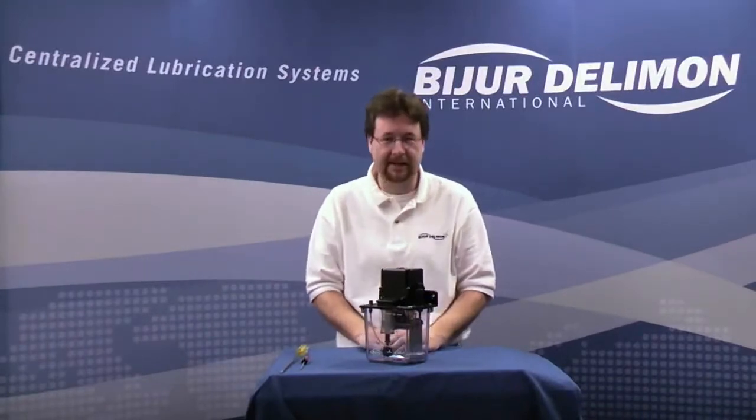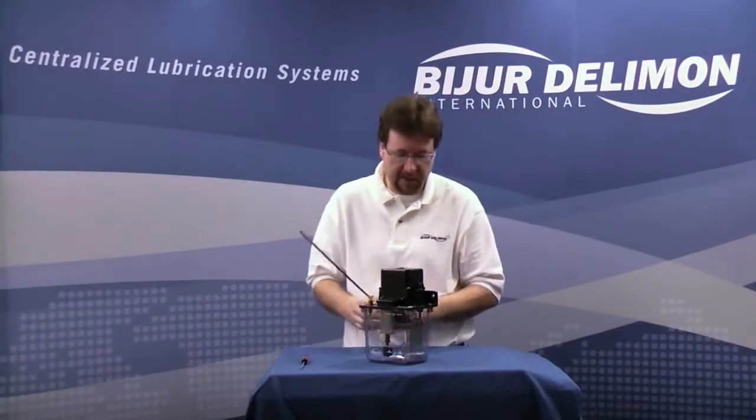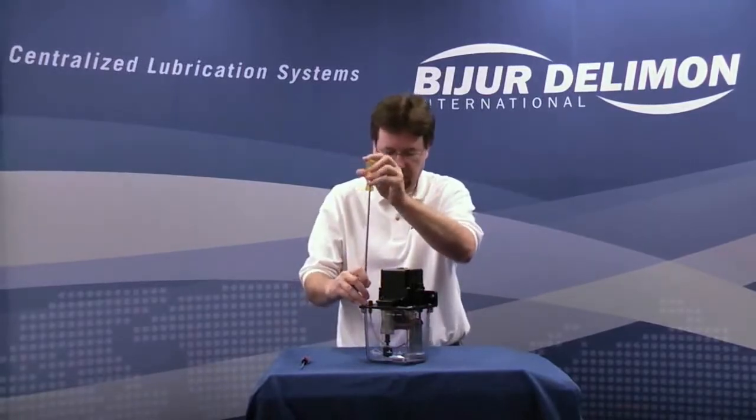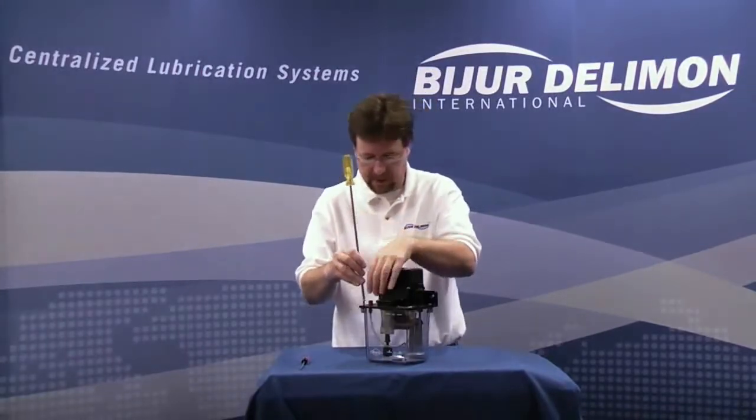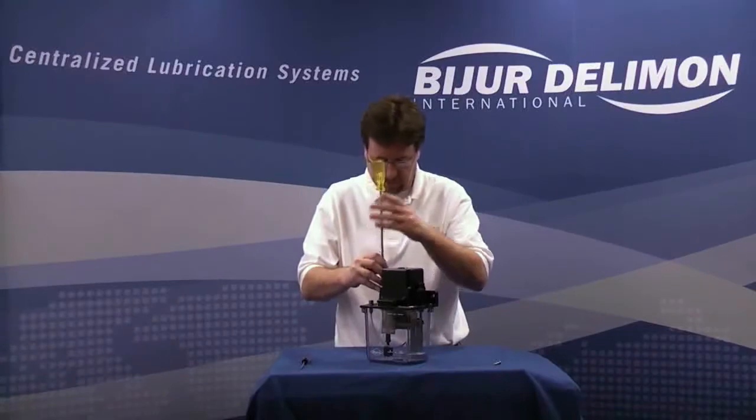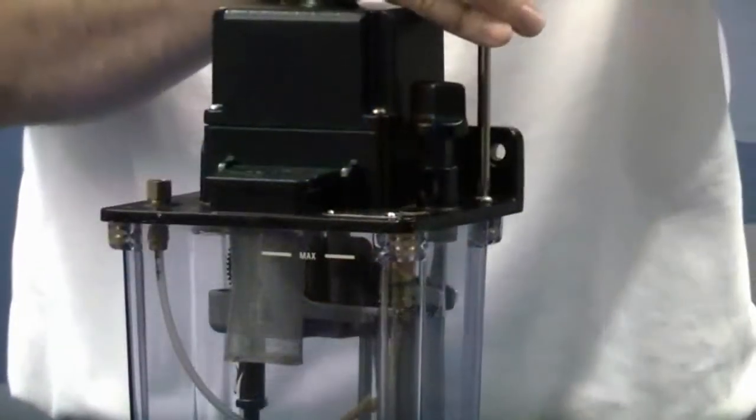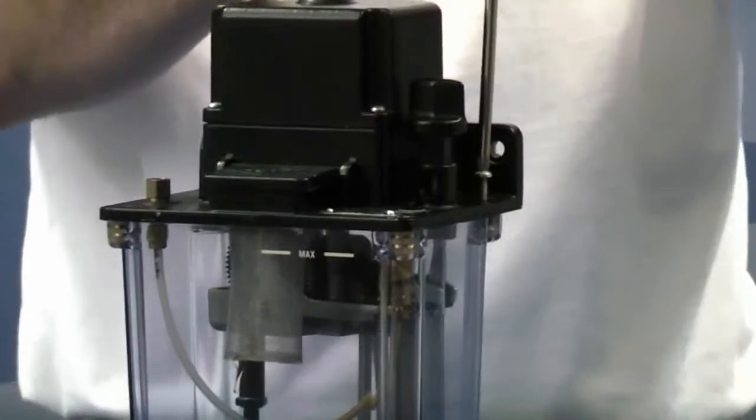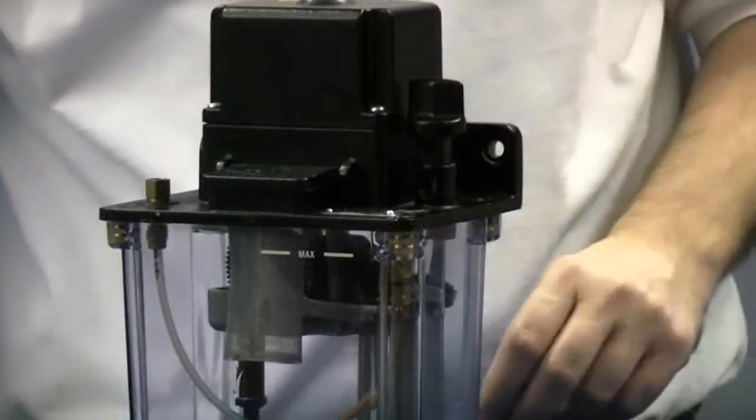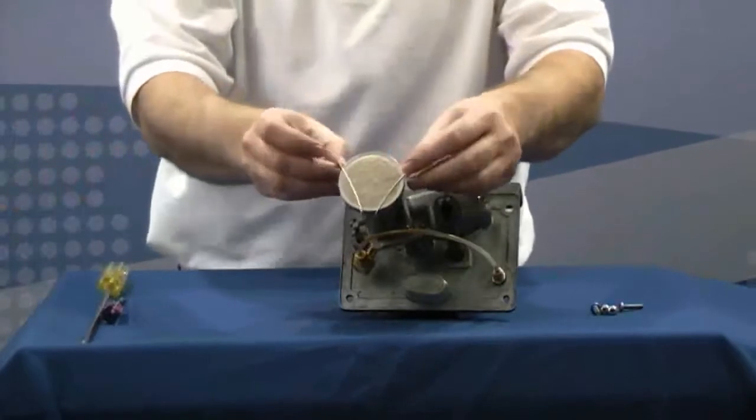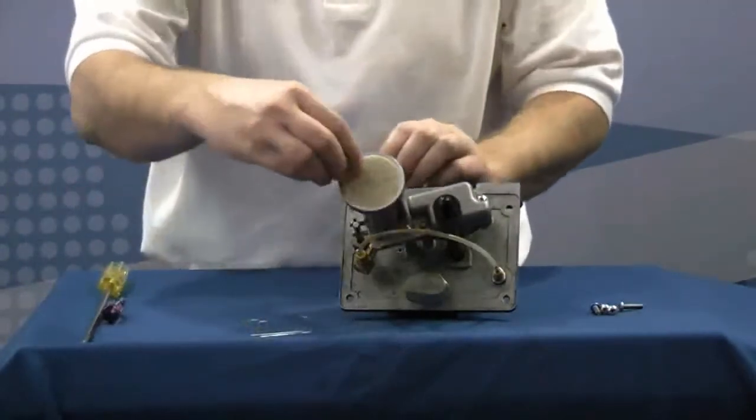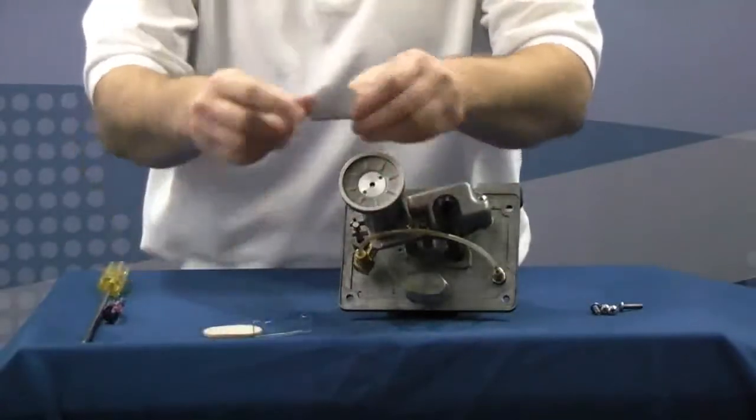Maintenance on the TMD5 is very easy. We'll start by removing and replacing the filter group. Remove the top four screws on the plates. Remove the unit from the reservoir. And we want to remove the filter. We'll just take off the clip, remove the felt and the filter screen.